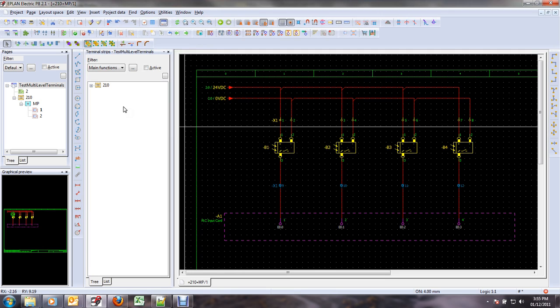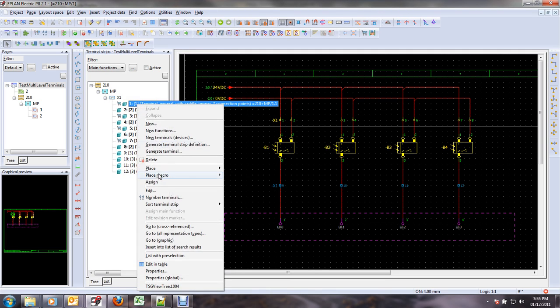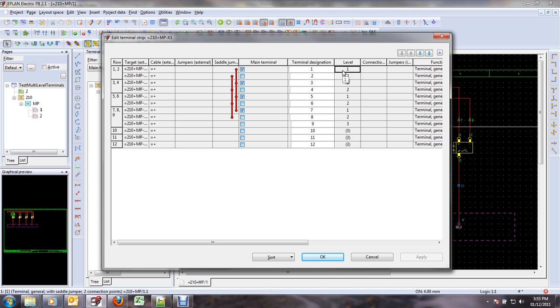But if I look at my terminal strip right now in the terminal strip editor, I can see that they are not properly ordered. For EPLAN to consider them as one single terminal, they would need to be ordered at the level 1, 2, 3, 1, 2, 3, and so on.